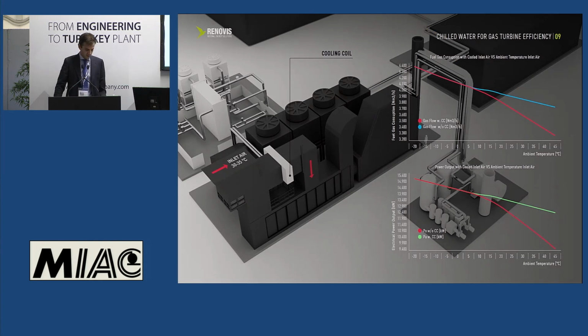In fact, in this slide, we see how the temperature of the inlet air entering the gas turbine affects its performance. In summer, the high temperature of the intake air produces a significant drop in the performance of the gas turbine. However, this phenomenon can be avoided by cooling the inlet air by means of a chilled water-air heat exchanger located in the intake chamber and supplied with cold water produced free of charge by the absorption chiller I mentioned before.